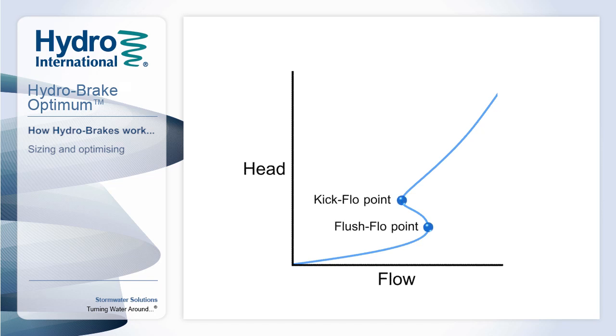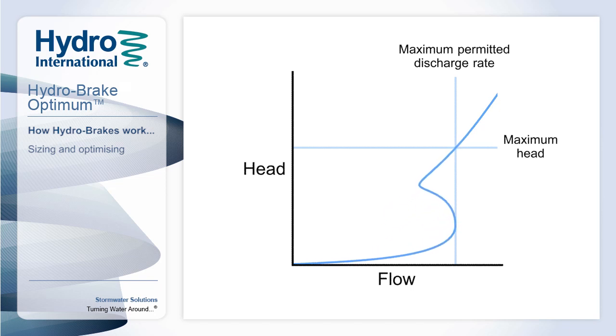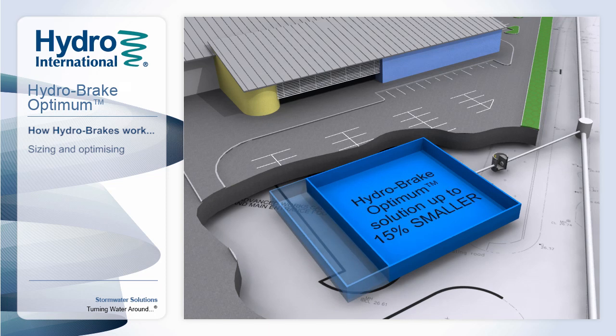The manipulation of the Flush-Flo and Kick-Flo relative to the maximum permitted discharge rate and maximum head is of particular relevance to engineers, as it can significantly influence the final system design. For optimum hydraulic performance, the Flush-Flo point can be matched to the permissible discharge rate from the system, allowing more water to pass through the unit during the earlier stages of a storm. This can reduce upstream storage requirements by up to 15% when compared to other vortex flow control devices, offsetting the cost of the device and significantly reducing overall project costs.